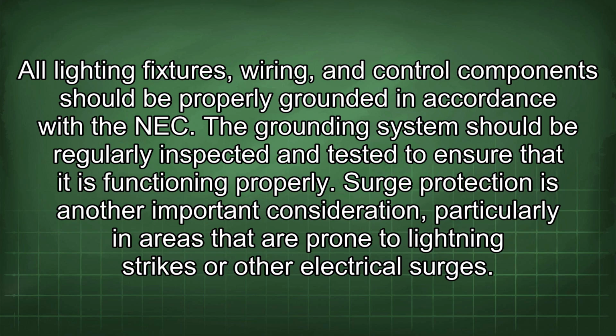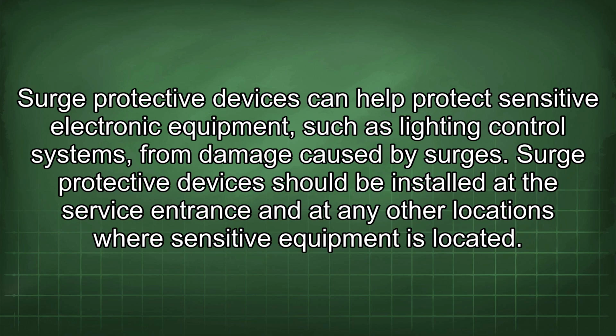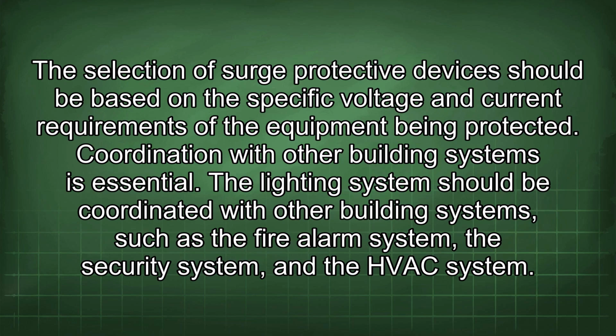Surge protection is another important consideration, particularly in areas that are prone to lightning strikes or other electrical surges. Surge protective devices can help protect sensitive electronic equipment, such as lighting control systems, from damage caused by surges. These devices should be installed at the service entrance and at any other locations where sensitive equipment is located. The selection of surge protective devices should be based on the specific voltage and current requirements of the equipment being protected.